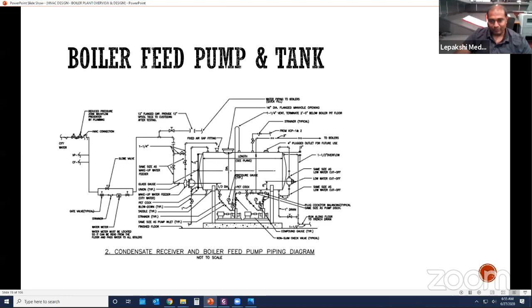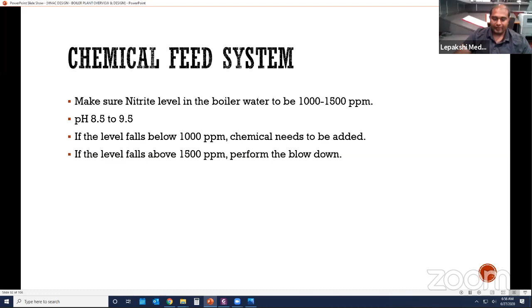If the level falls under 1000 ppm, they'll take measurements, check it, and dump some more chemical into the water. That protects the boiler, giving it more life.